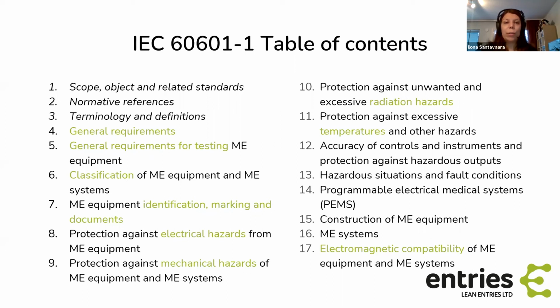Chapter 5 is about general requirements for testing. Chapter 6 gets you started on classification of ME equipment and ME systems. So some of those classifications that you will need to do affect the coming chapters, because if you classify that your device is in one category or is not in one category, then when you are reading the requirements later on, if it says that it's only for this and this, then you know immediately whether you need to even read this chapter. Chapter 7 contains multiple requirements regarding identification, marking, documentation, so instructions for use, for example.